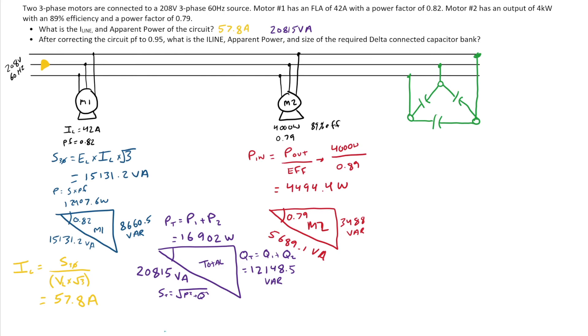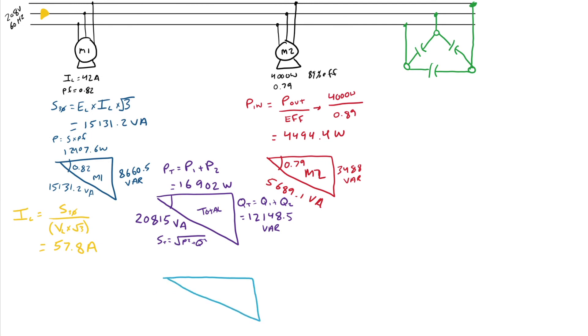So I like to draw a new power triangle. Call this my new power triangle. I know my power factor is 0.95. I'm told that's what I'm correcting it to. And I know my wattage won't change. 16,902 watts. Awesome. So now what I can do is I can do my standard triangle math. I like to go 16,902 divided by 0.95 to get a new VA of 17,791.6 VA.